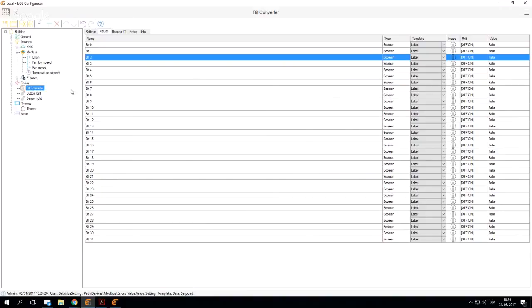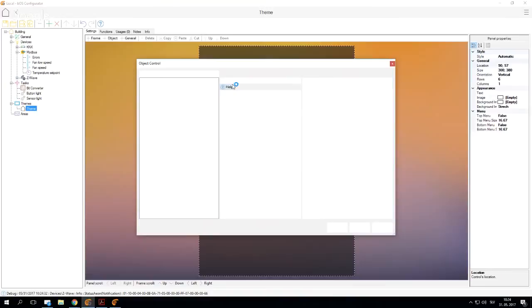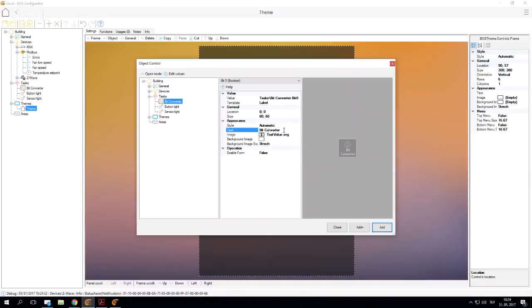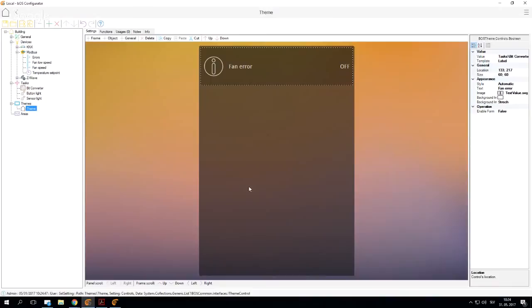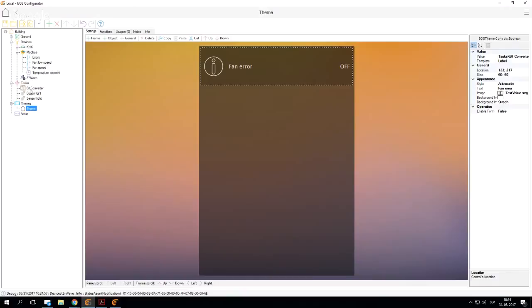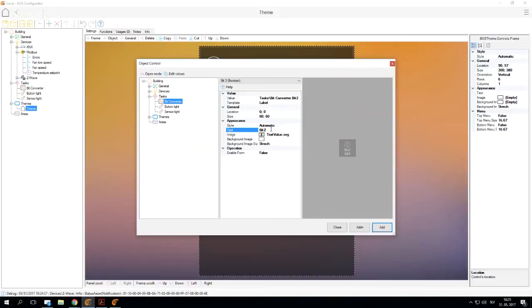In this case, I can simply drag and drop our Bit Converter here, select our bit, let's say bit 0, and say the text is going to be fan error. Now every time something is going to be wrong on that address of our Modbus device, we're going to actually see here displaying a fan error. Let's say we're also going to add bit 2 and just say temperature error.